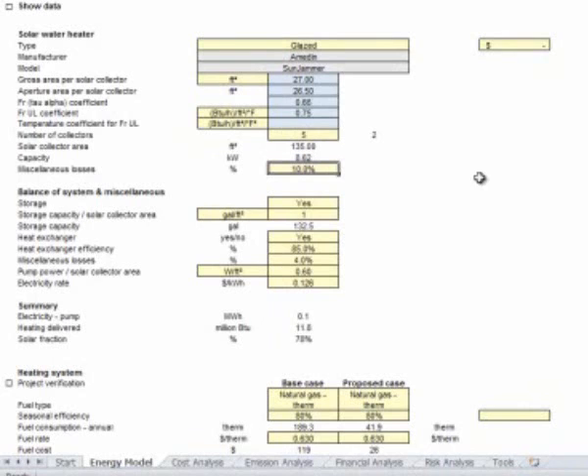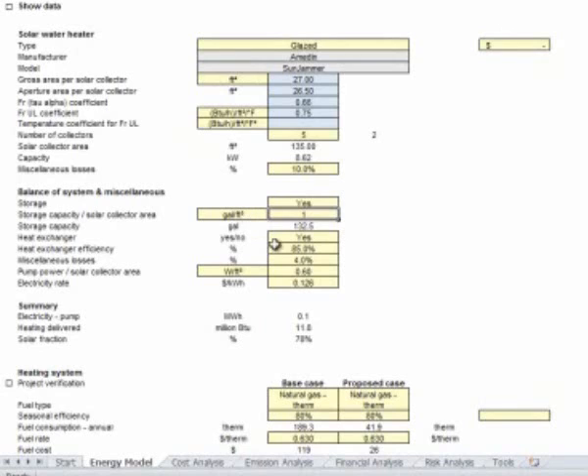Then I'm going to say, okay, I need 132 gallons minimal. It's a storage capacity for us in central Illinois. We're going to want to leave it as a one-to-one ratio, one square foot per gallon of water for collection. Heat exchanger is yes. By definition, we'd like to leave our heat exchange option as 85%. That doesn't always mean that's the case, but that's a good offset.